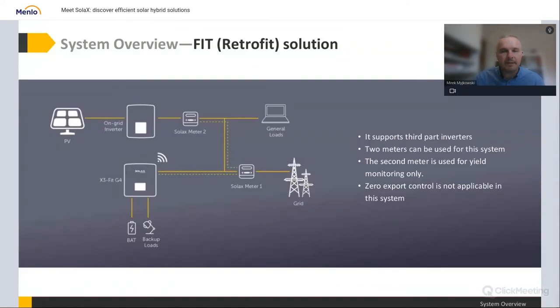Any third-party inverter can be used. We're not communicating with it in any way. We can measure its energy flows with another SolaX meter—that's possible, not necessary, but possible. It has to be a meter with address 2, but it's not really necessary. Our meter 1 will see that power, and we will use it to charge the battery.